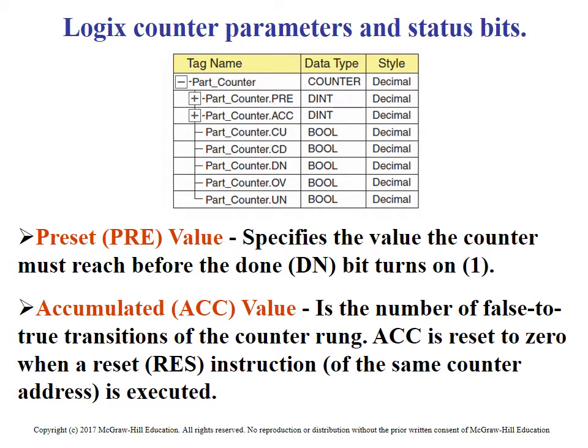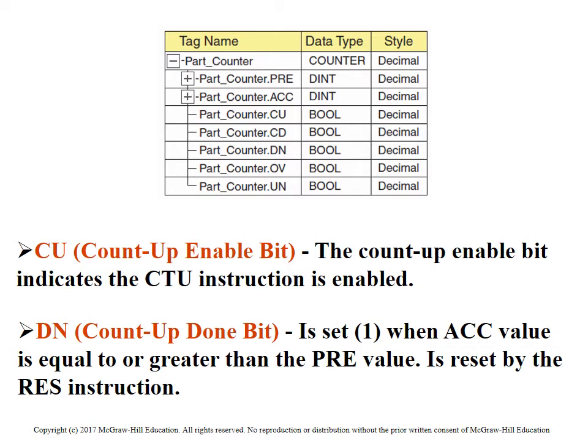Here are all the pieces: we've got the preset word — double integer, so 32 bits. Accumulated value is also a double integer, again 32 bits. And then all these components here are individual bits and boolean: counter up, counter down, done bit, overflow, and underflow. The preset value specifies the value the counter must reach before the done bit turns on. Like the 500 series, the accumulator value must be equal to or greater than the preset value for the done bit to turn on.